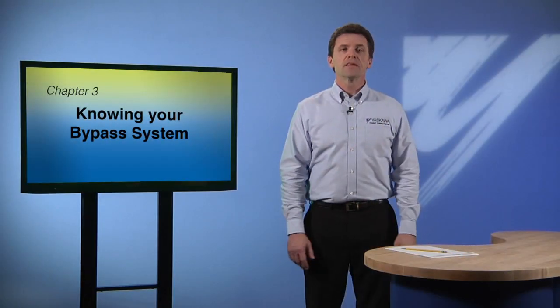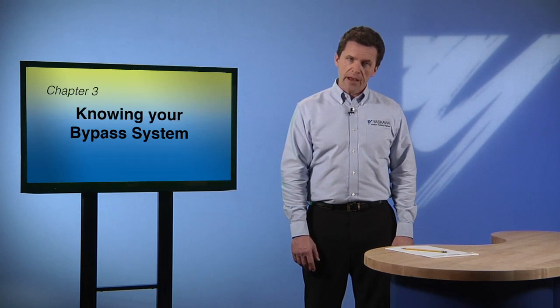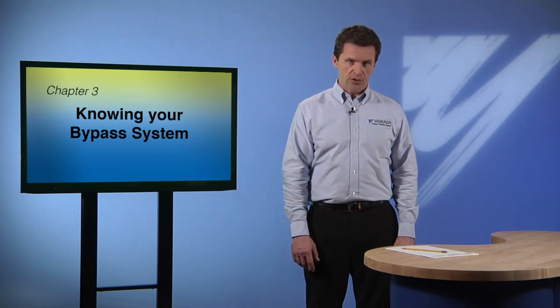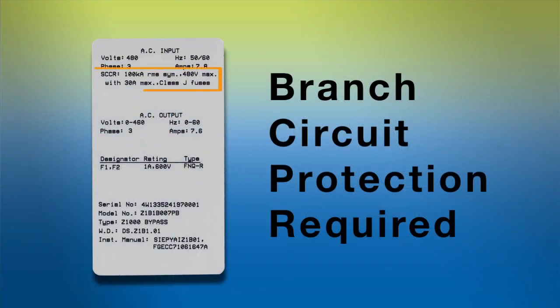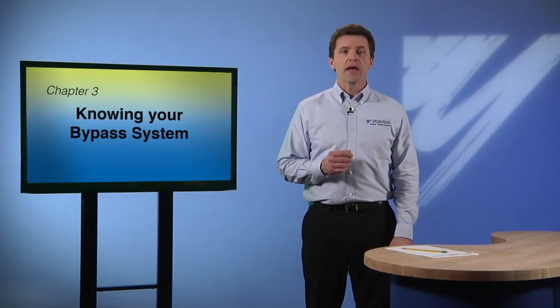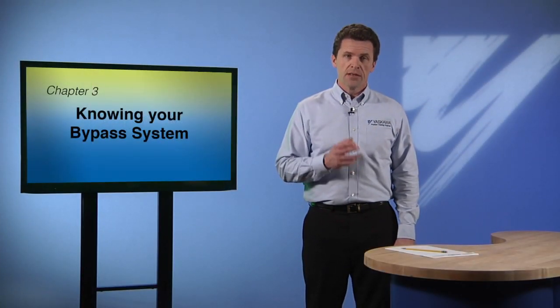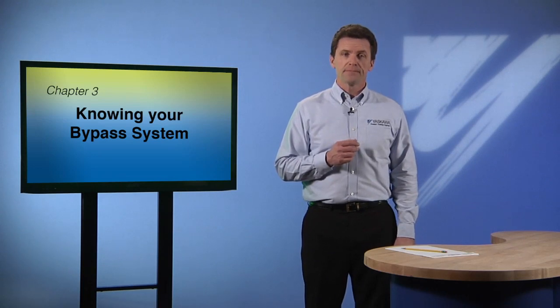We also need to check the nameplate on the bypass to make sure the bypass is equipped with branch circuit protection. If the nameplate indicates that no protection is present, some form of branch circuit protection must be added before you can proceed with setup. Now, if you purchased a bypass that is equipped with a circuit breaker option, this need has already been met.